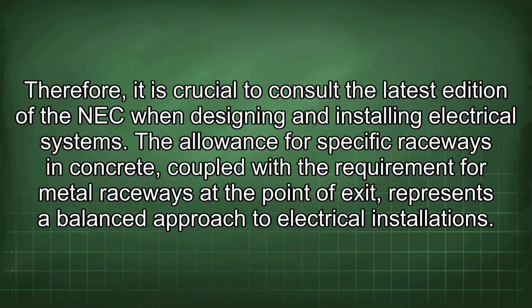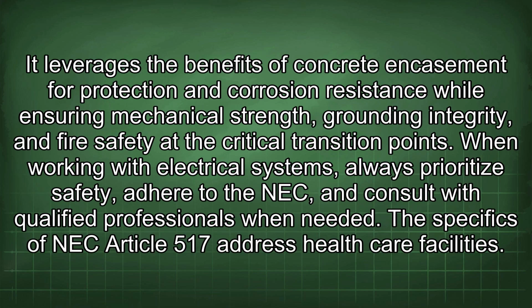The allowance for specific raceways in concrete, coupled with the requirement for metal raceways at the point of exit, represents a balanced approach to electrical installations. It leverages the benefits of concrete encasement for protection and corrosion resistance while ensuring mechanical strength, grounding integrity, and fire safety at the critical transition points. When working with electrical systems, always prioritize safety, adhere to the NEC, and consult with qualified professionals when needed.